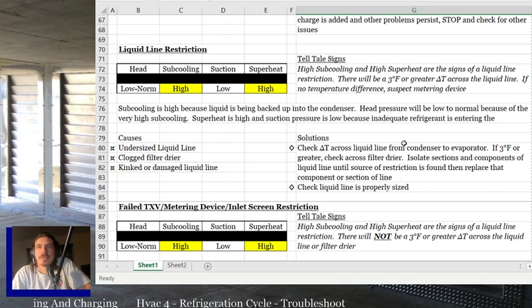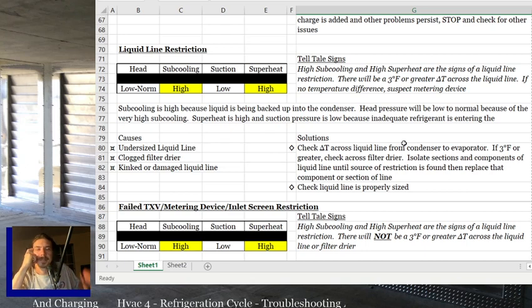All right, liquid line restriction. A liquid line restriction and a failed metering device look exactly the same for the most part. So these next two, you're going to see almost the exact same diagnostics. The trick is determining which one it is, and the liquid line is the first one you should always rule out. You always rule out a liquid line restriction and then assume you have an issue at the metering device.